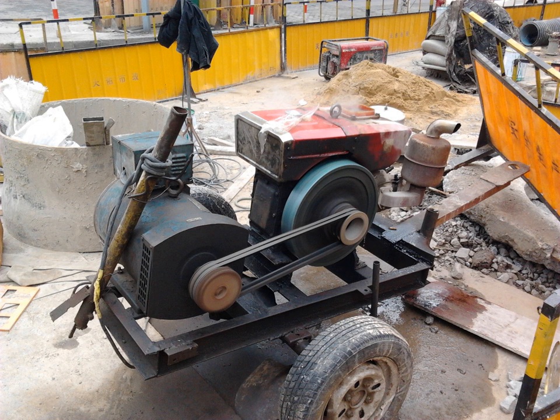Using portable generators in garages, or near open windows or air conditioning vents can also result in carbon monoxide poisoning. Additionally, it is important to prevent backfeeding when using a portable engine generator, which can harm utility workers or people in other buildings. Before turning on a diesel or gasoline-powered generator, users should make sure that the main breaker is in the off position, to ensure that the electric current does not reverse.